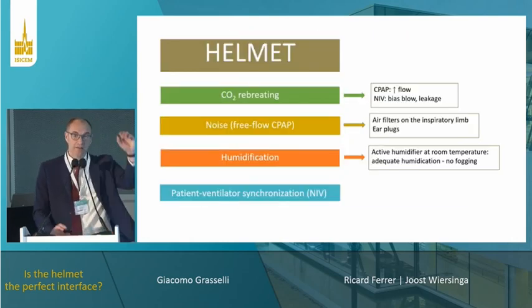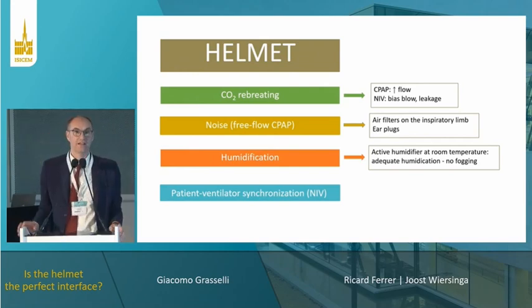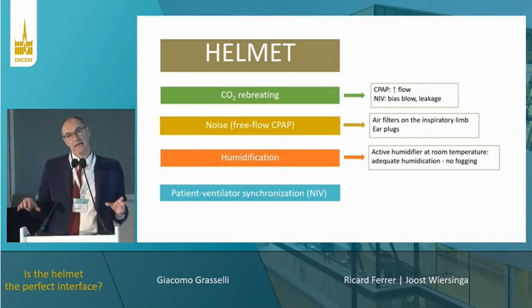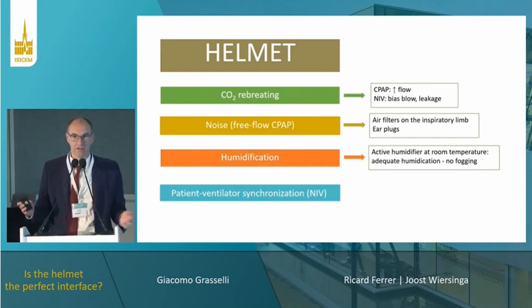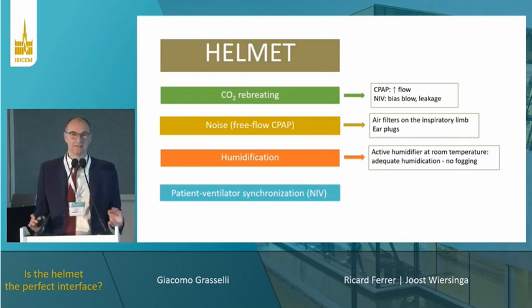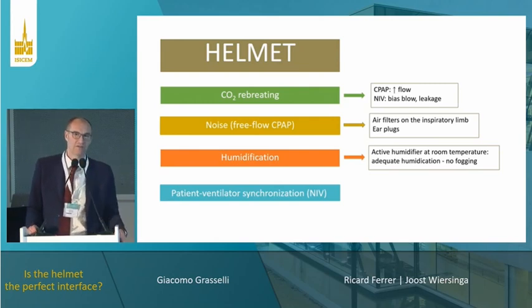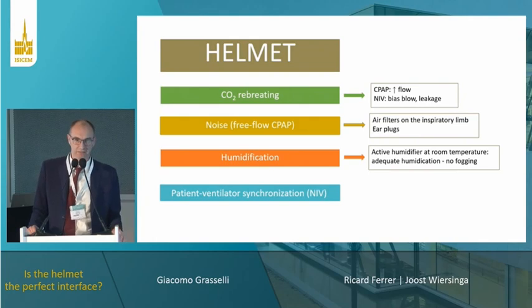So for CO2 rebreathing, it's quite easy. You need a high enough fresh gas flow through the helmet in order to wash out the CO2 and avoid rebreathing. So if you are doing free-flow CPAP, it's commonly said that you need a flow above 30 liters per minute, but you can increase it a bit. For noise, you can put earplugs or you can put filters on the inlet. Yeah, you laugh, but it's a problem.